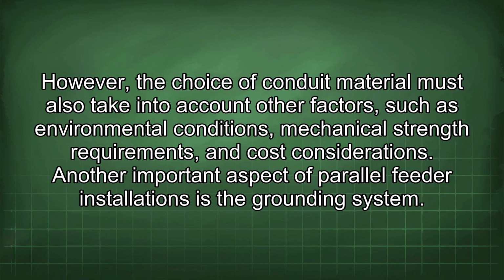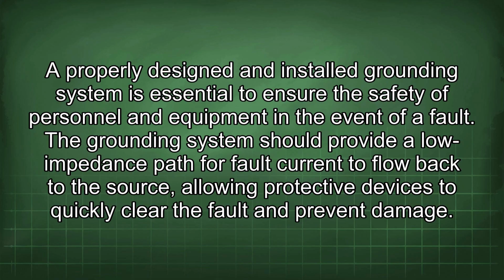However, the choice of conduit material must also take into account other factors such as environmental conditions, mechanical strength requirements, and cost considerations. Another important aspect of parallel feeder installations is the grounding system. A properly designed and installed grounding system is essential to ensure the safety of personnel and equipment in the event of a fault. The grounding system should provide a low impedance path for fault current to flow back to the source, allowing protective devices to quickly clear the fault and prevent damage.